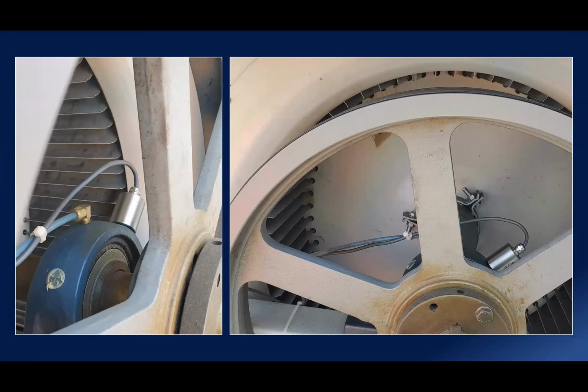And to give you an idea of what the sensor looks like, now it's hard to get scale. This is the cooling tower that the guy was lubricating in that picture I had shown earlier. So this allows me to show two things: what the sensor looks like, completely stainless steel, how it gets mounted onto a bearing. Now, because we're monitoring friction, we're using ultrasound, which is very directional. We just have to be mounted somewhere on that bearing. We're not measuring movement, so we're not concerned about different axes, which is one of the biggest benefits about ultrasound, is that it's very directional.